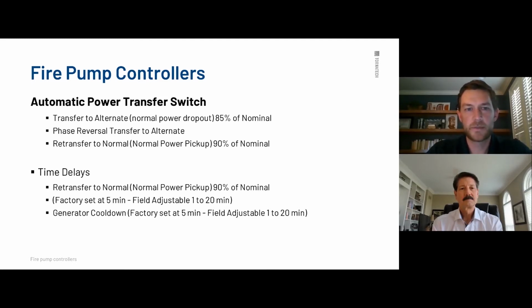So this is going to explain sort of the process for transferring. If your nominal power drops down to 85% of what it should be, it's going to switch over to alternate power, because the control panel is going to say that the power is not healthy, and it's going to turn on your generator. It's going to switch over to the alternate side, and you're going to be running on the diesel generator at that point. Also, it will switch over if you have a phase reversal on your normal power side.